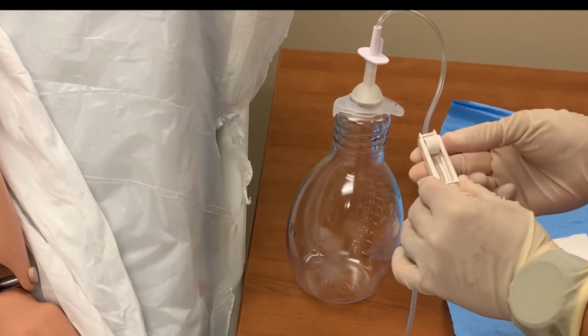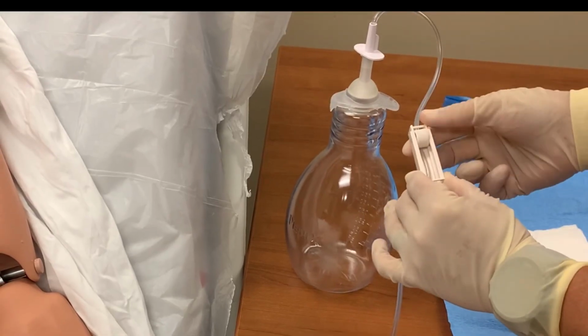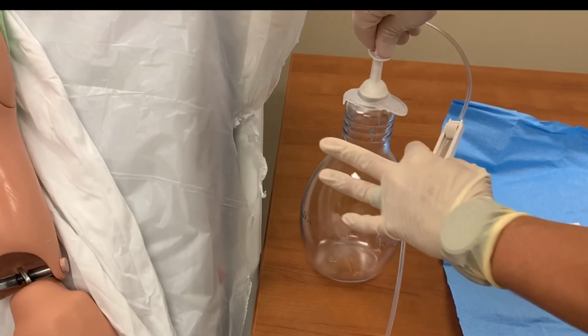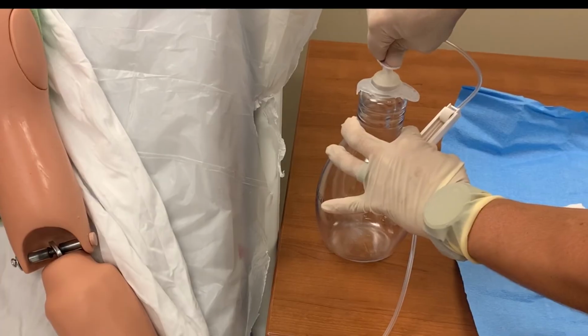On the bottle's tubing is a roller clamp. After removal from the package, the roller clamp should be closed. The roller clamp allows the nurse to control the amount of negative pressure being exerted on the pleural space at any given time. With the roller clamp closed, pressing the T-plunger into the bottle will activate the negative pressure.